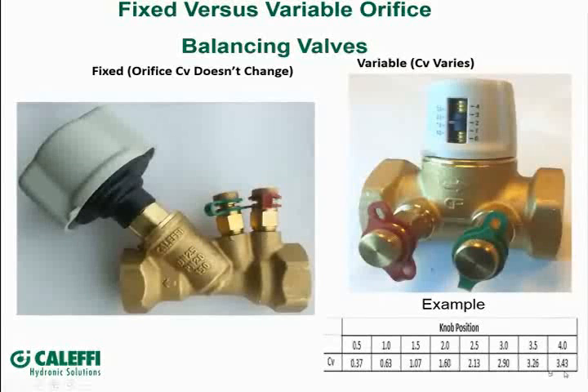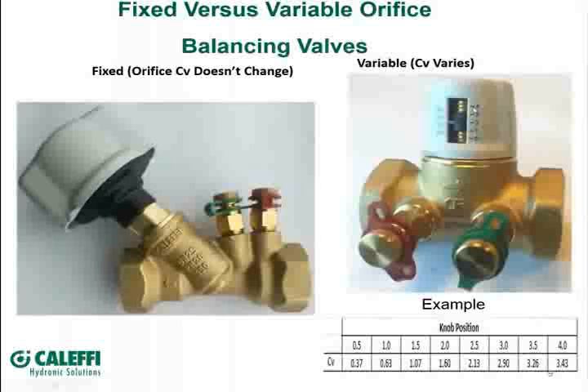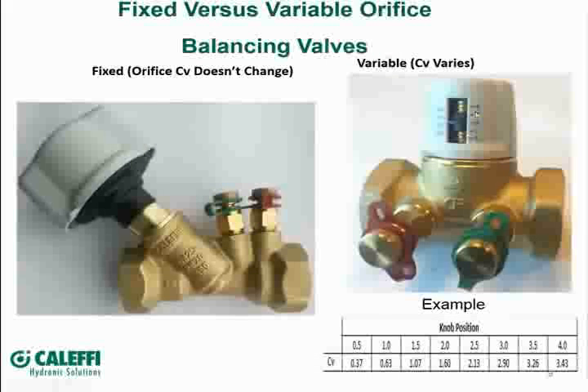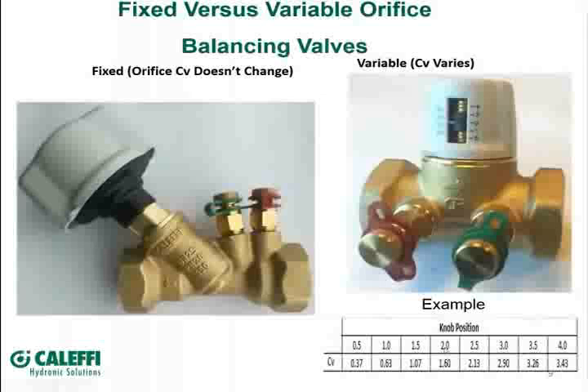If you go all the way out to the far right-hand end and select this valve based on the full open position, you would have a CV of 3.43, which indicates this valve all the way open at position number four. Now as you crank this valve down and adjust the different numbers on the scale on the knob, it does change the CV of that valve. For instance, if you put it at position number two, the CV has now changed to 1.60.